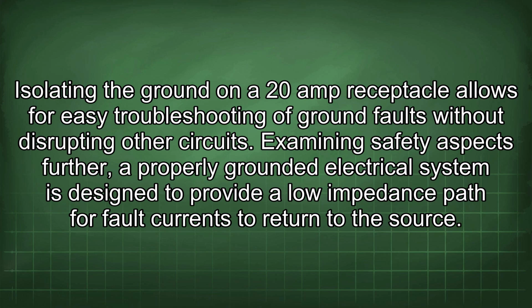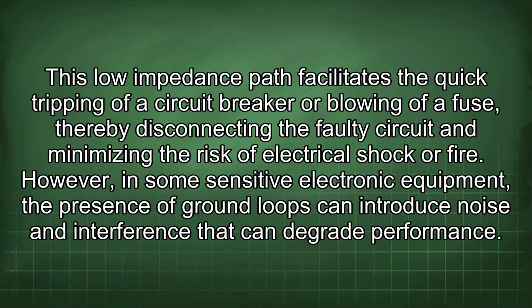Examining safety aspects further, a properly grounded electrical system is designed to provide a low impedance path for fault currents to return to the source. This low impedance path facilitates the quick tripping of a circuit breaker or blowing of a fuse, thereby disconnecting the faulty circuit and minimizing the risk of electrical shock or fire.